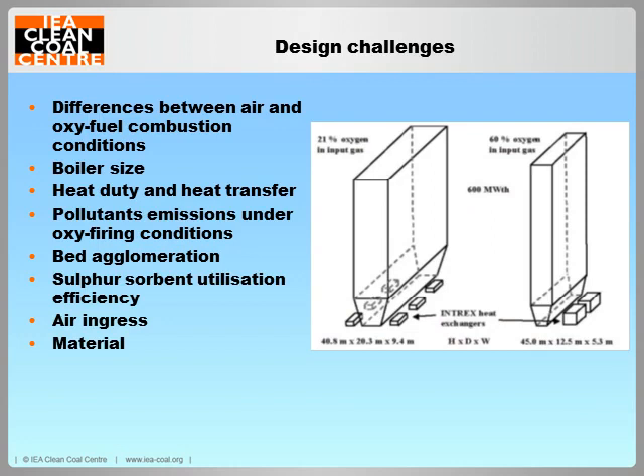For example, in oxygen combustion, the flue gas volume flow decreases considerably, resulting in significant size reduction in the furnace, cyclone, convection path, and other equipment, as illustrated here. On the other hand, increasing oxygen content leads to higher combustion temperature, which will increase the need of heat transfer in the furnace and its share of the overall boiler heat duty. This creates a challenge to manage the furnace temperature levels and to locate and develop designs for heat exchangers in the hot loop of the Oxy-CFB boiler.